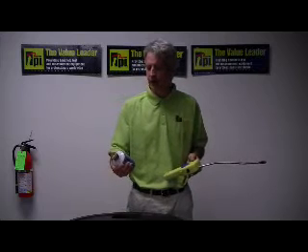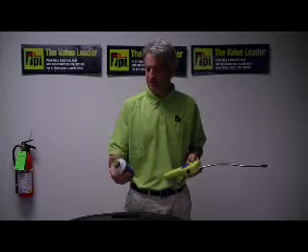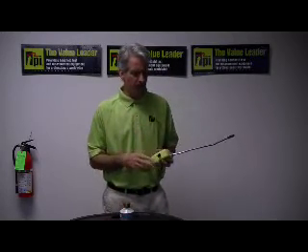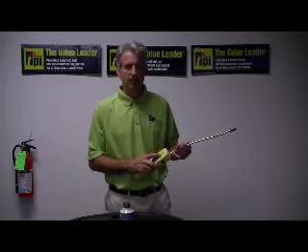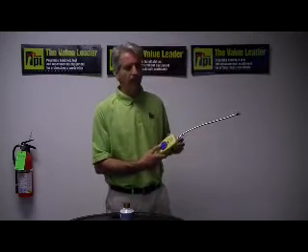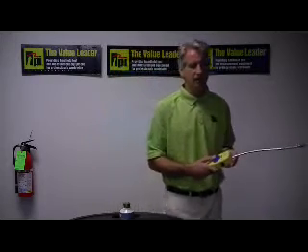The particular source we're working with today has a leak rate equivalent to 0.17 ounces a year of R134A. Since this unit is only rated down to 0.2, we'll actually have to put it on high sensitivity to find this leak. So I turn the unit on high and turn the thumb adjustment clockwise until I get a steady tick rate.